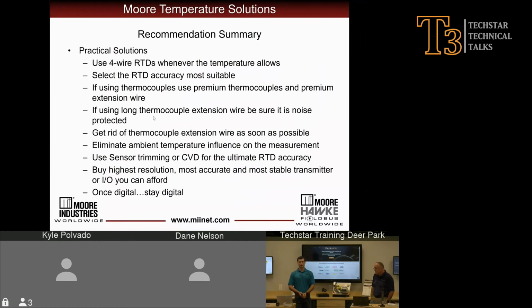So going back over what we discussed, some of our techniques to measure temperature more accurately include using a 4-wire RTD whenever the temperature allows. One of the constraining factors to RTDs is that they can only go up to a certain temperature, and most temperature specifications are around 800 to 900 degrees Fahrenheit. So we recommend using that RTD whenever the process temperature allows it. There are sometimes where you can't get away from using thermocouples. And so if you are using thermocouples, use premium thermocouples or premium extension wire. If you're using long thermocouple extension wires, make sure that it's noise protected so that it's not susceptible to the VFD noise or the motor noise that we discussed.